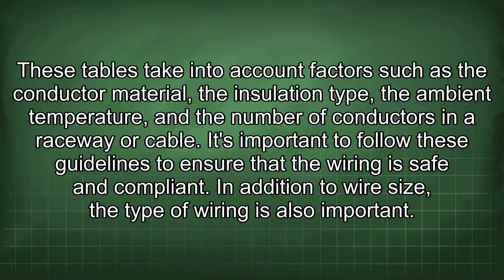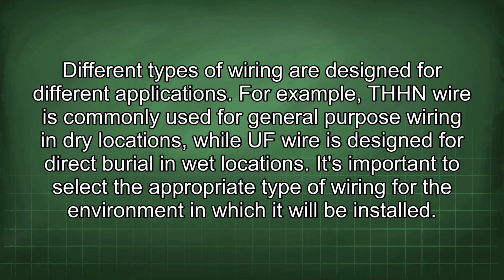It's important to follow these guidelines to ensure that the wiring is safe and compliant. In addition to wire size, the type of wiring is also important. Different types of wiring are designed for different applications. For example, THHN wire is commonly used for general-purpose wiring in dry locations, while UF wire is designed for direct burial in wet locations.